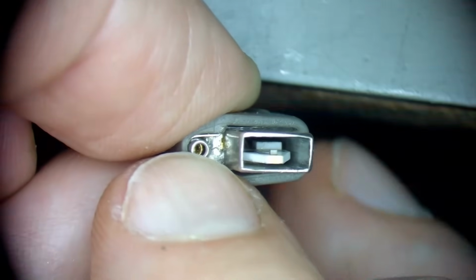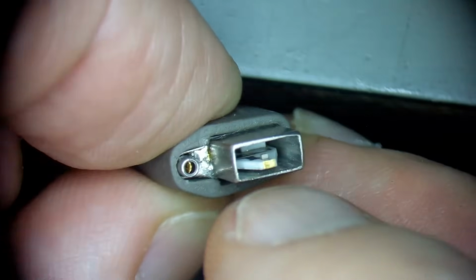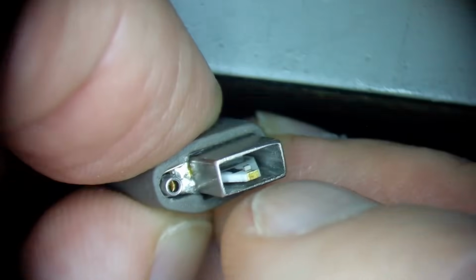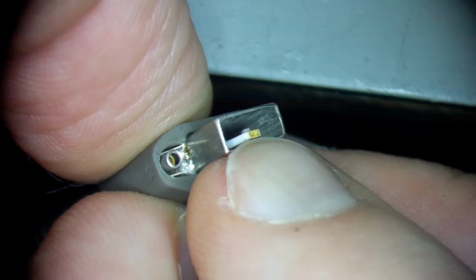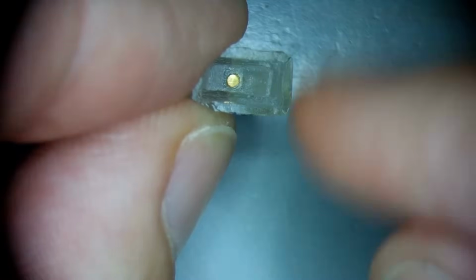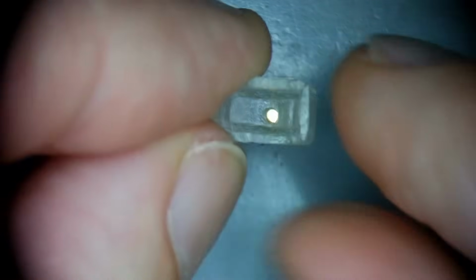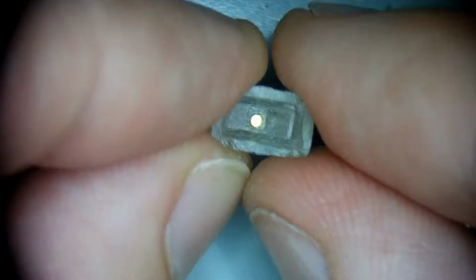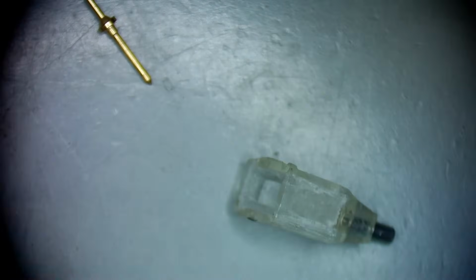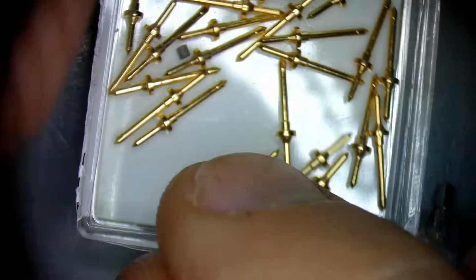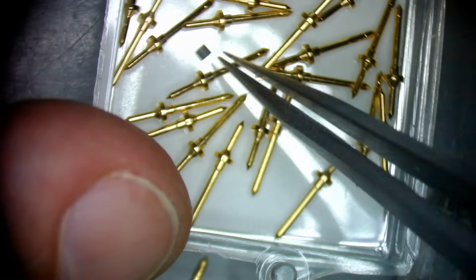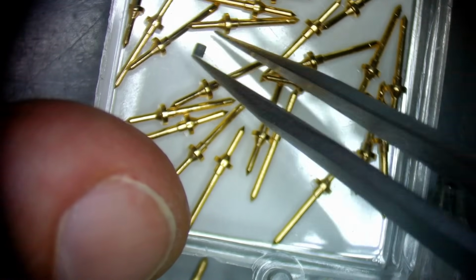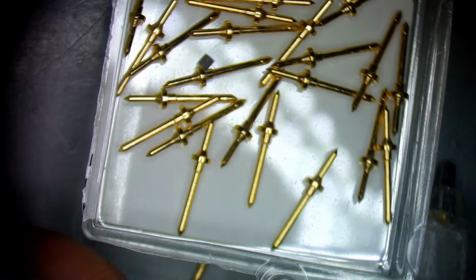Now let's look at it this way. This is another socket for grounding attachment, and there we can see active probe electronics on a substrate. Is it ceramic or something else? I'm not entirely sure. And here is this gold-plated pad on the edge, which should be coupled with that gold-plated pad on the back end of the socket. It is also offset from center this way, so I put a mark on this side, and it is recessed, as you can see. So between them there should be a conductive rubber or foam piece. Here it is, a cylindrical piece. So it should provide soft contact between those pads.